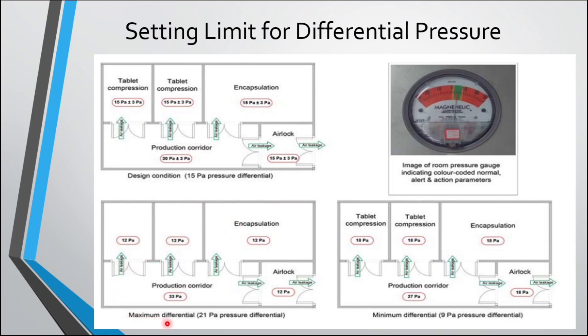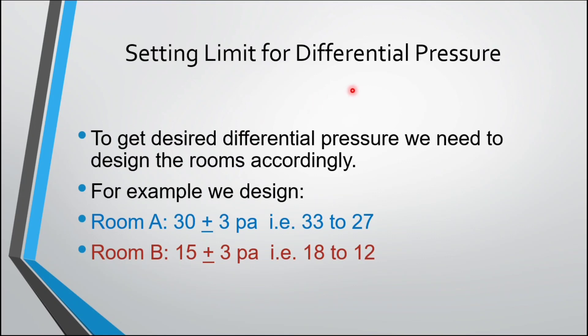Considering this design, the maximum differential pressure achievable is 21 Pascal and the minimum is 9 Pascal. Room A is designed at 30 ± 3 Pascal, so its maximum is 33 Pascal and minimum is 27 Pascal. Room B is designed at 15 ± 3 Pascal, giving an upper limit of 18 Pascal and a lower limit of 12 Pascal. Both rooms are grade D.